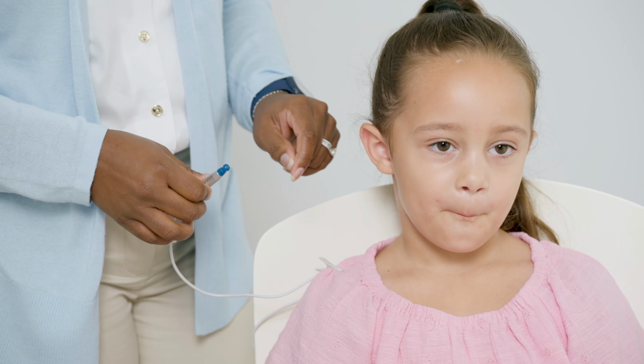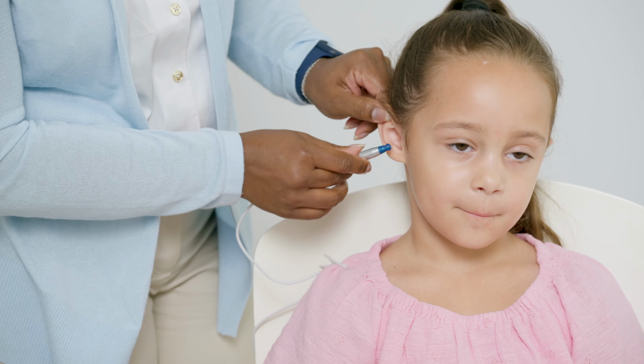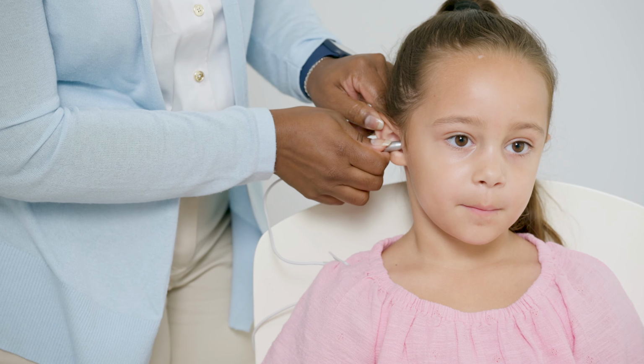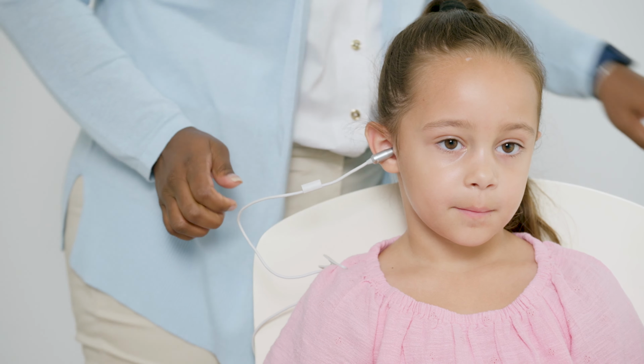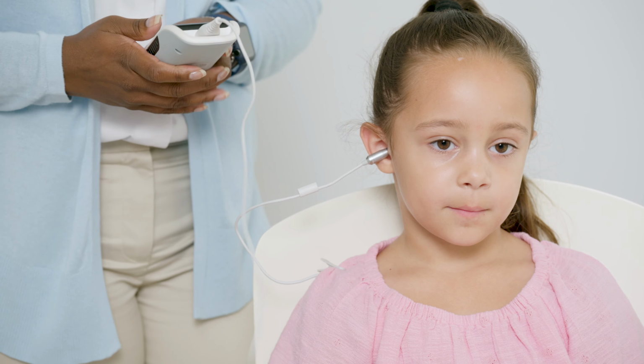To perform the test, the ear tip on the probe of the GSI Corti device must be inserted firmly into the child's ear canal. The probe fit should be secure enough that it stays in the ear without having to hold it in place.